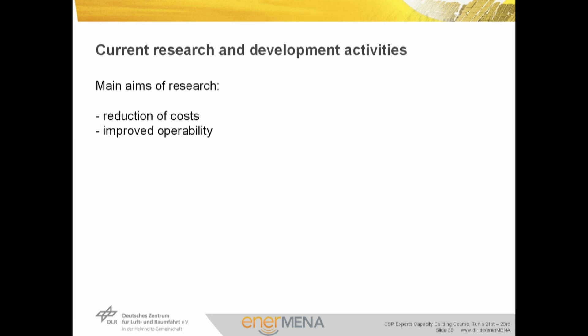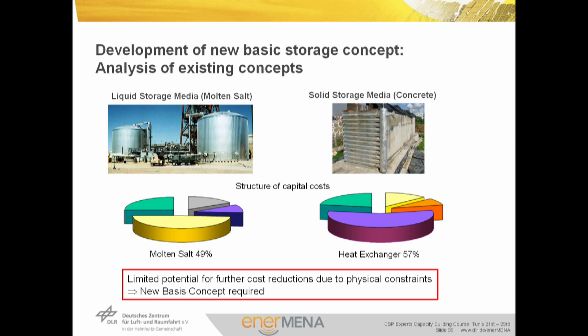Current research activities in storage technology focus on two aspects: reduction of costs and improvement of operability. Analysis of today's storage systems shows that for both two-tank molten salt storage and solid media storage systems, there is a single component that dominates costs — for molten salt, it is the investment in the salt itself; for solid media, it is the heat exchanger. In both cases, a significant reduction of these dominant cost factors does not seem possible, so a new basic storage concept is needed.